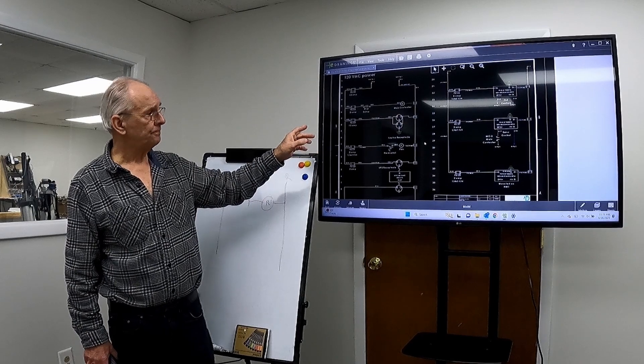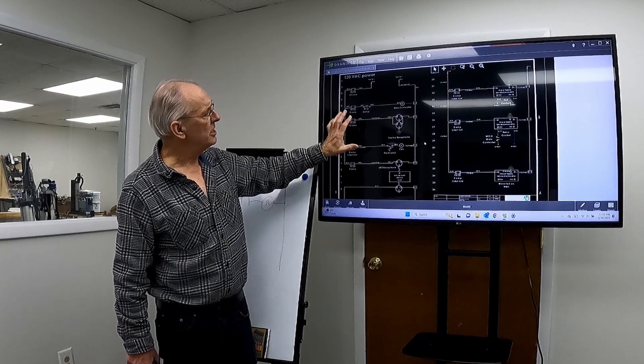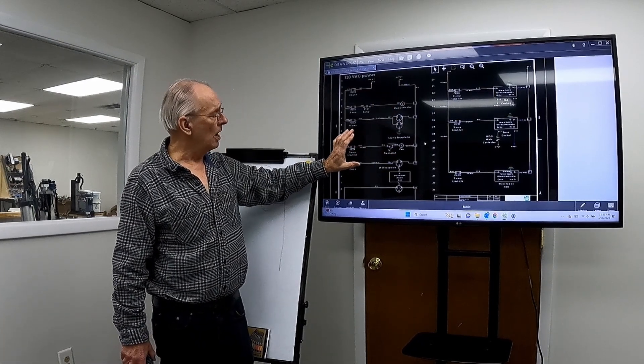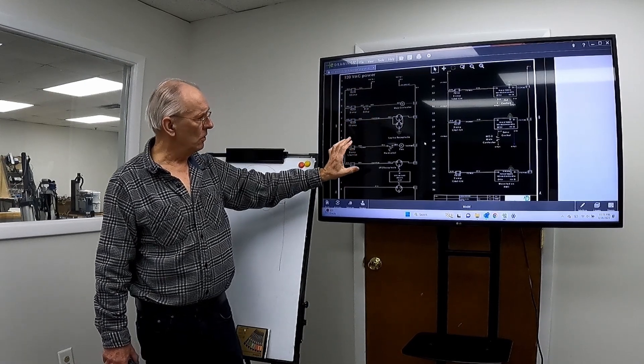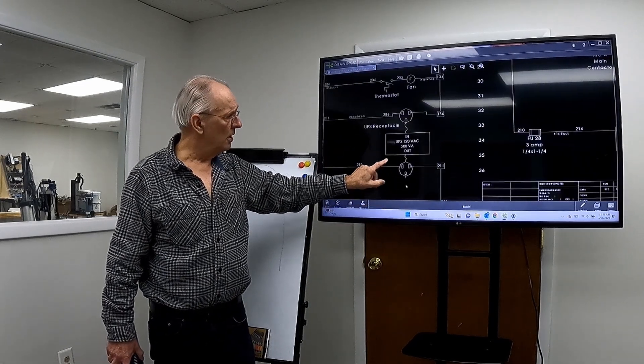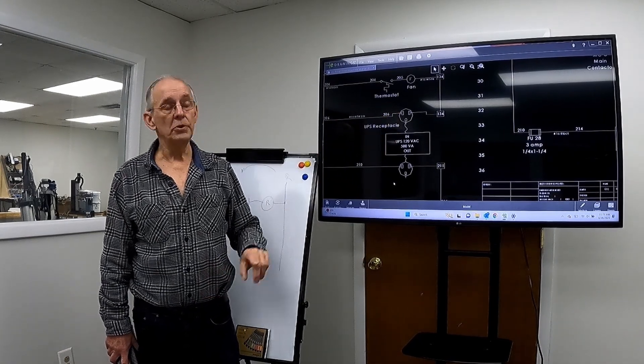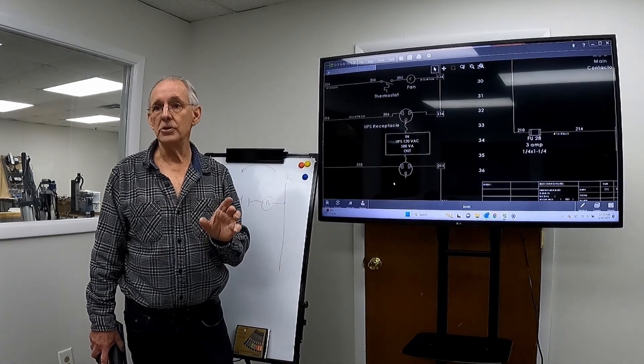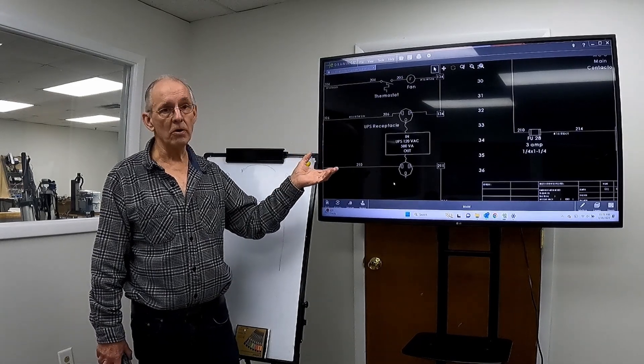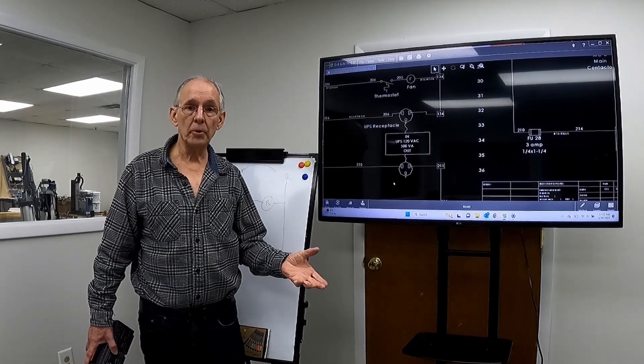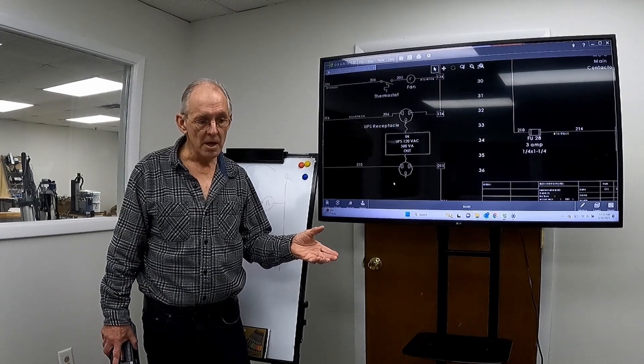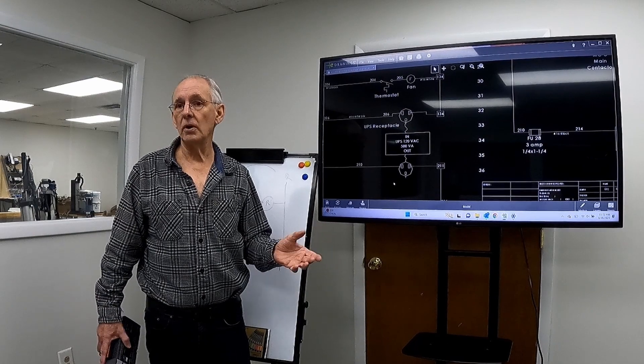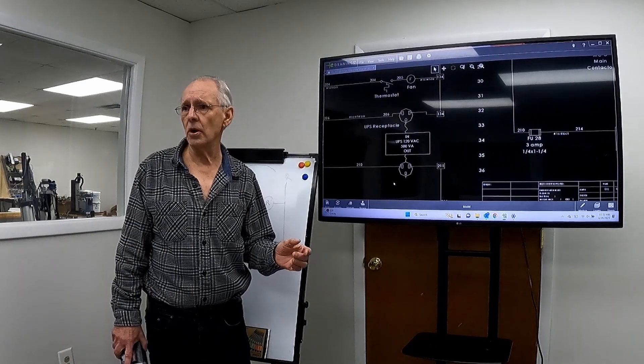And here, this again, we're in the 120 volt power, and we're operating power supplies. This is the AC power from the transformer that was in the previous page. So these are the things that run on 120 volt. Now you'll notice down here, we have a UPS. So we've got the UPS plugged into a receptacle which is fed from the transformer, and then the UPS creates power that is uninterruptible. So in other words, if we have a power failure, this small amount of 120 volt power stays on. The purpose of that is that in a power failure, in the case of this machine, everything would lose position. And so when the power came back on, you'd have to rehome all the axes and take everything out of the machine and start it up again.